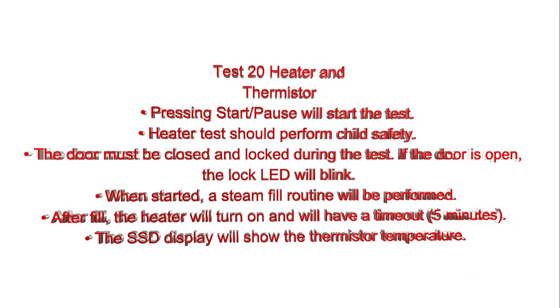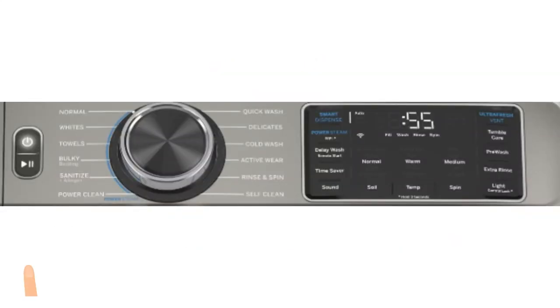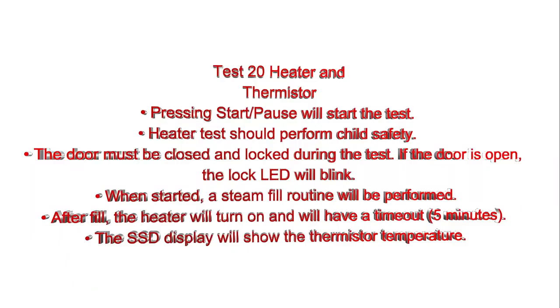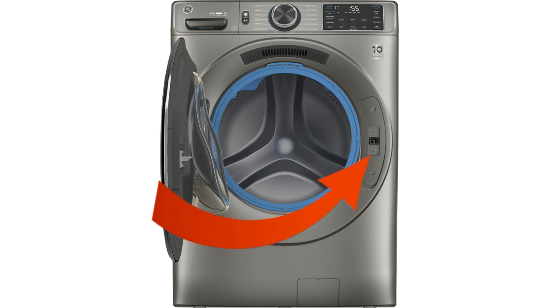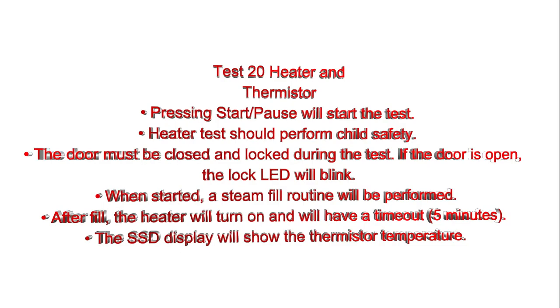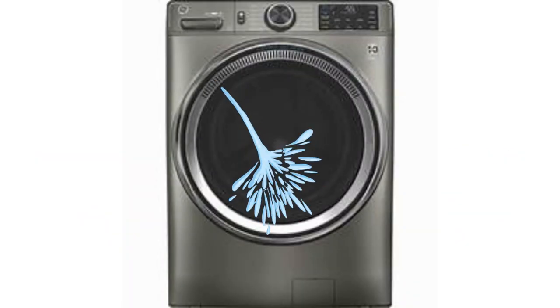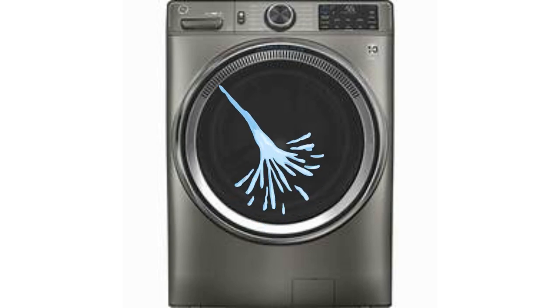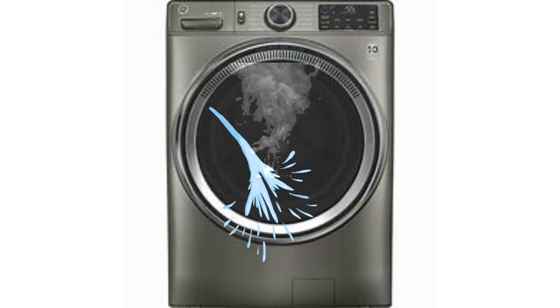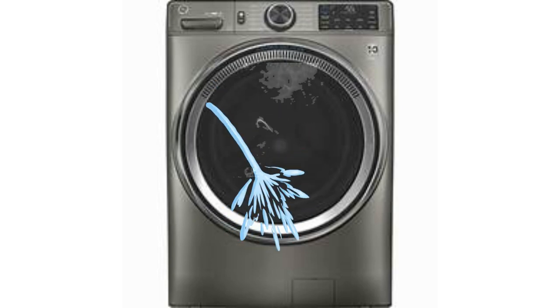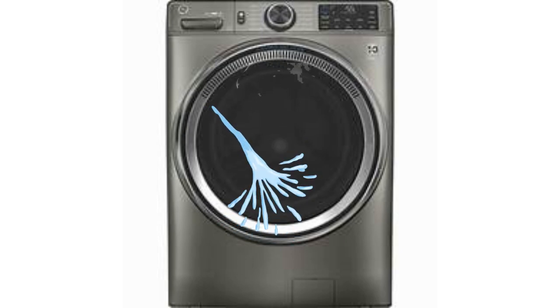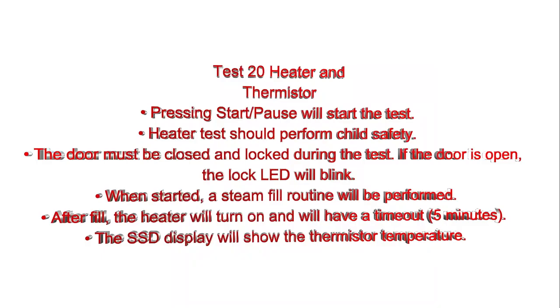Test mode 20, heater and thermistor. Pressing start/pause will start the test. Heater test should perform child safety. The door must be closed and locked during the test. If the door is open, the lock LED will blink. When started, a steam fill routine will be performed. After fill, the heater will turn on and will have a timeout, 5 minutes. The SSD display will show the thermistor temperature.